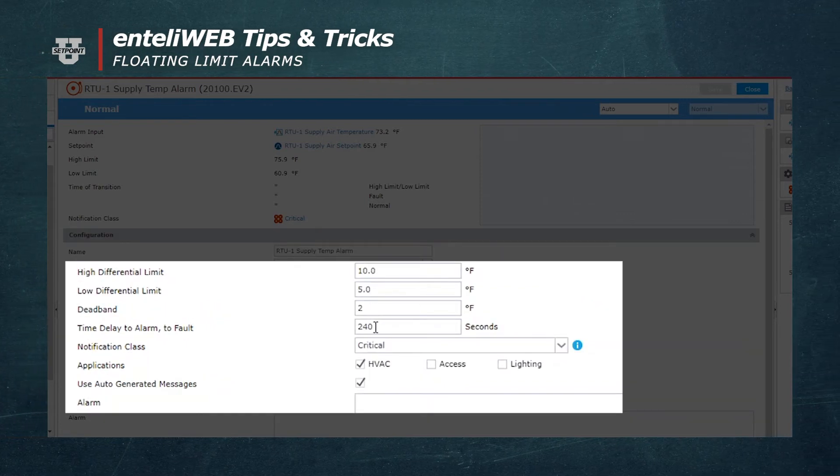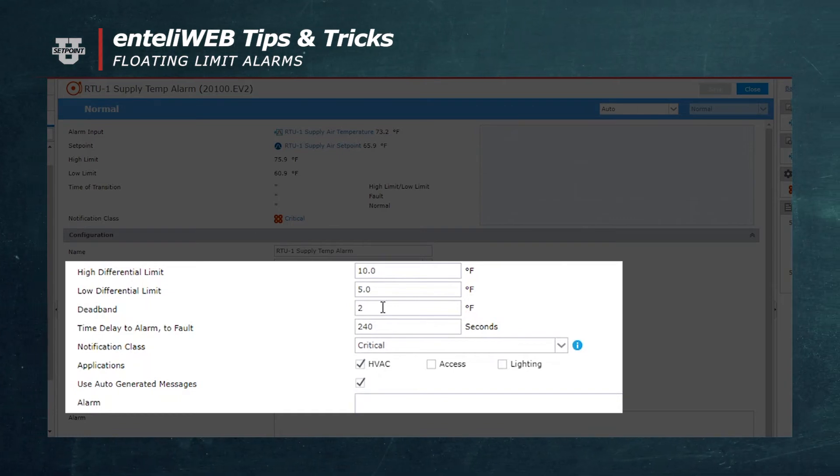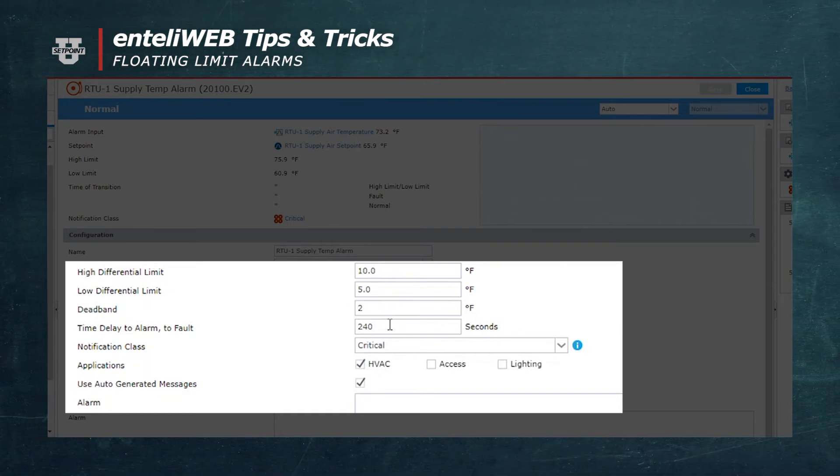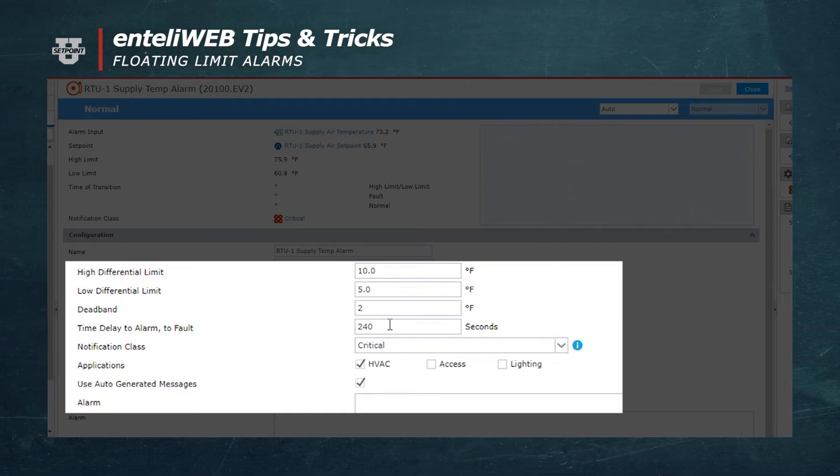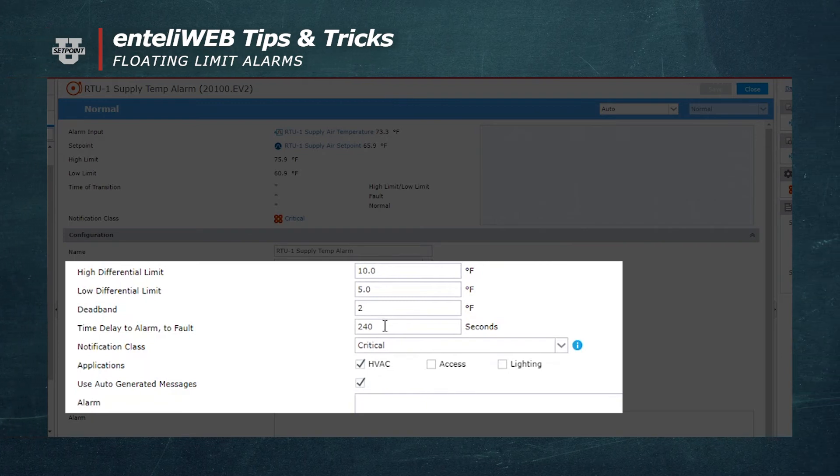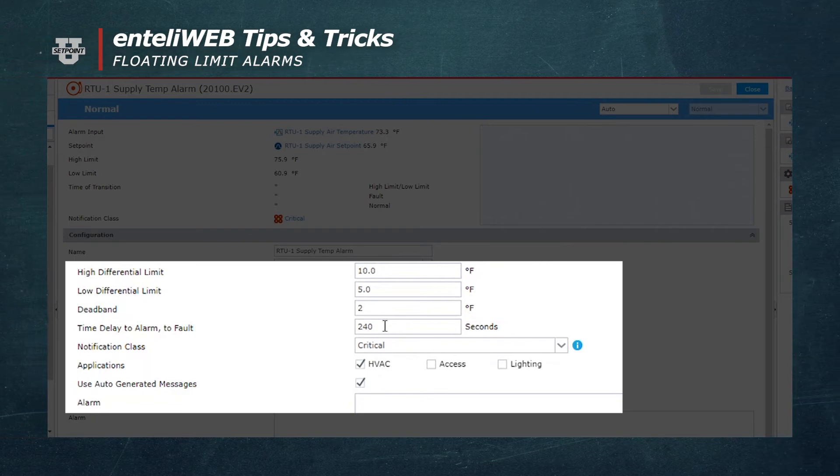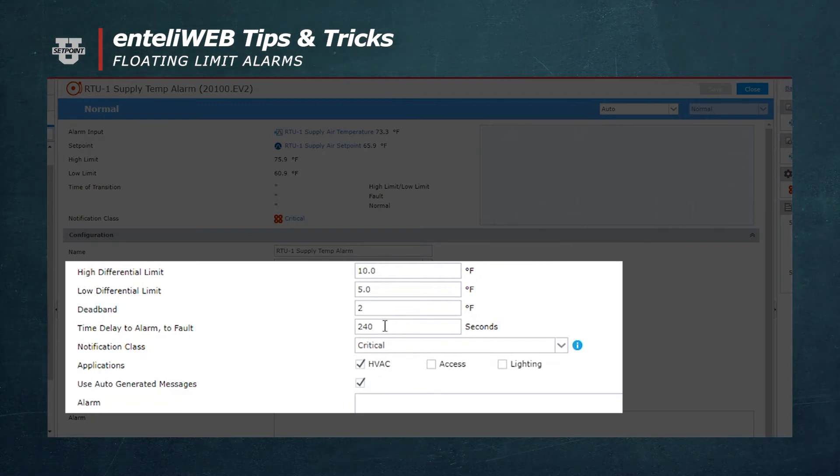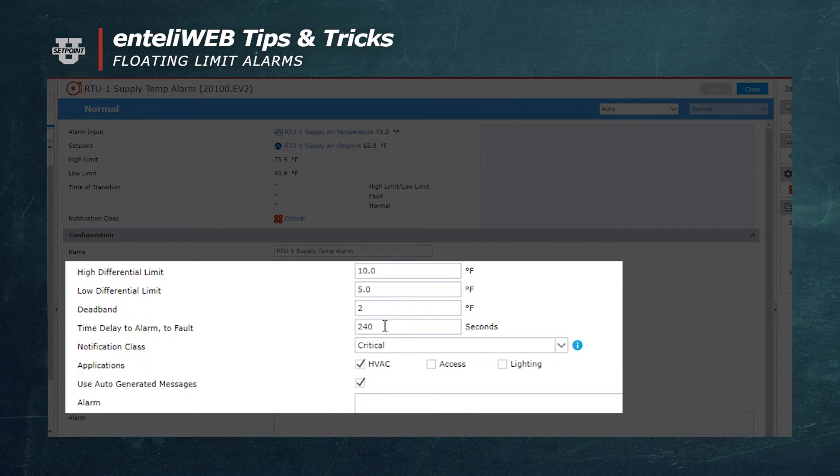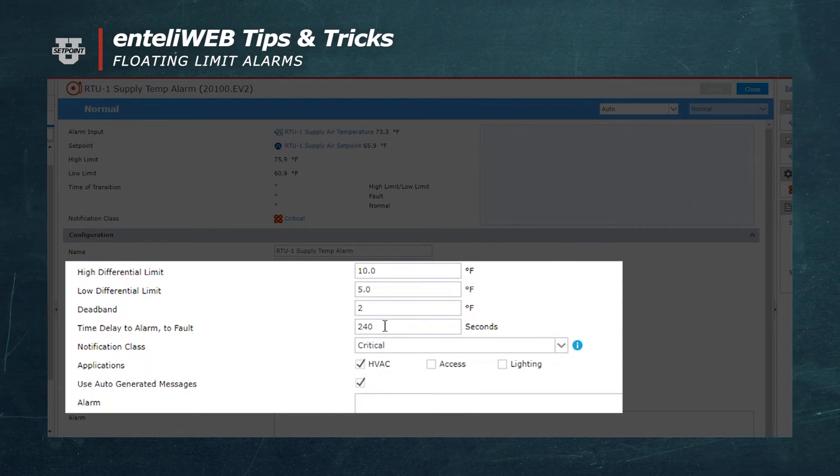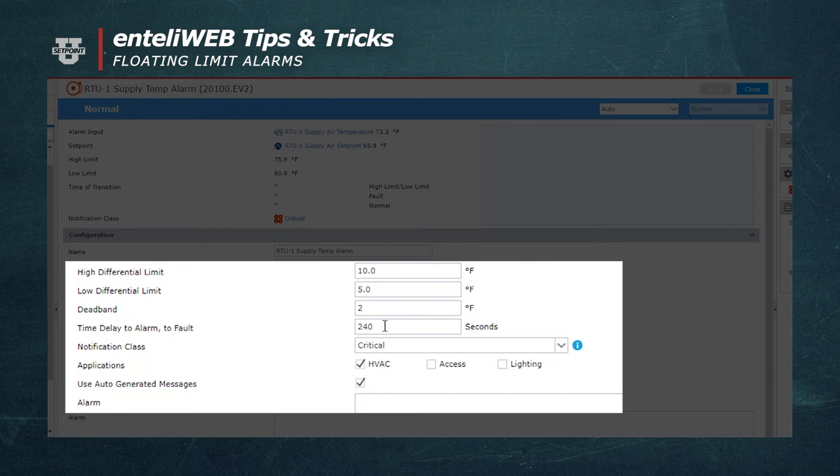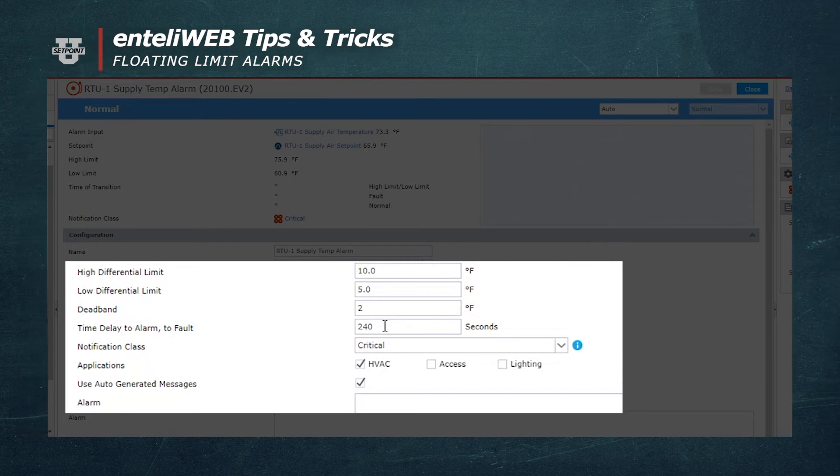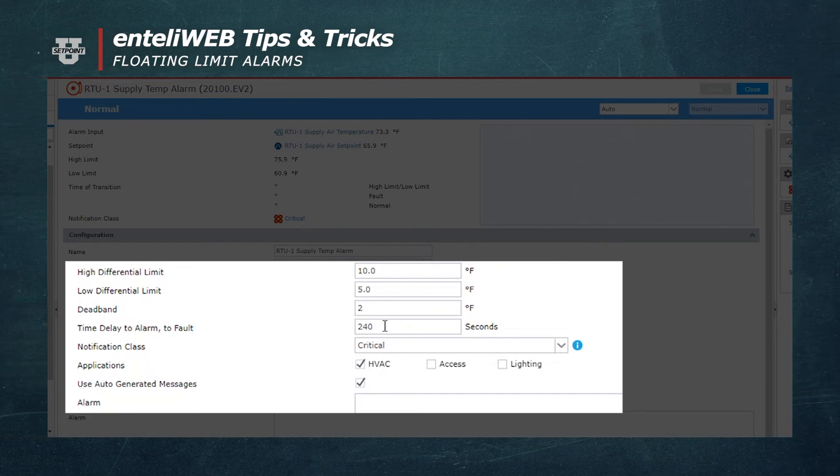The time delay for this alarm is 240 seconds. 240 seconds would give it plenty of time to come within range based on startup of the unit or some other thing like hot water supply not being available or chilled water.